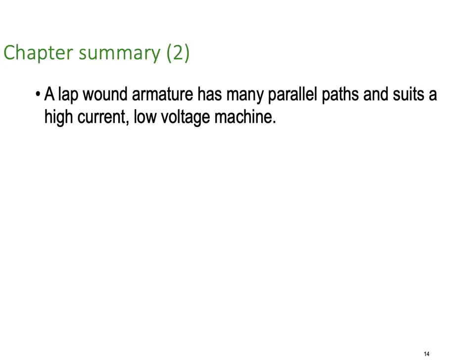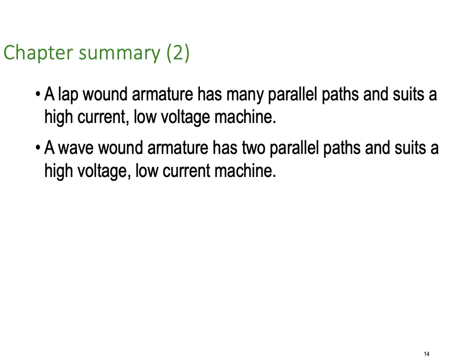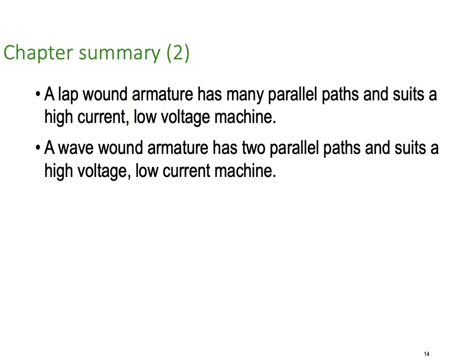A lap-wound armature has many parallel paths and suits a high current, low voltage machine. A wave-wound armature has two parallel paths and suits a high voltage, low current machine. The magnetic field in a generator can be produced by permanent magnets for smaller machines, or by field coils supplied by either an external DC source or by the generator itself. If by the generator itself, it will need some residual magnetism to get that field up and running.